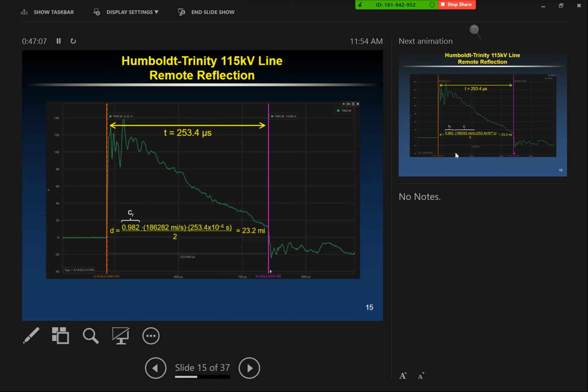You plug in your relative speed of light factor. For this line, we'd energize the line and figure out, from the reflection off the remote end, what that factor is. It came out to 0.982 for this 115 kV line. You multiply that by the actual speed of light in miles per second, multiply by your time, and divide by 2 since that's the round trip travel between the fault and the remote end. We get 23.2 miles.